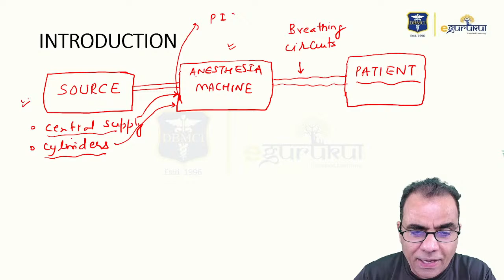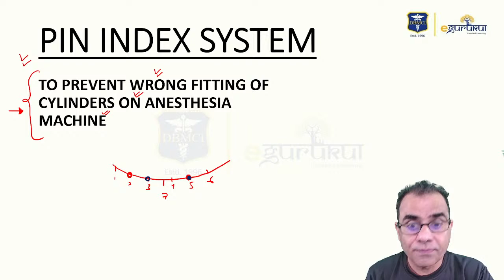Fine. So this is how gases from the source have reached the anesthesia machine, and at the anesthesia machine we have ensured that the wrong gas is not delivered to the patient, because delivering the wrong gas, I told you, delivering 100% nitrous oxide is definitely going to kill the patient. So now gases have reached the anesthesia machine. Now what happens in the anesthesia machine to these gases? That we'll discuss in this section. Anesthesia machine gas flow: how the gases flow in the anesthesia machine.